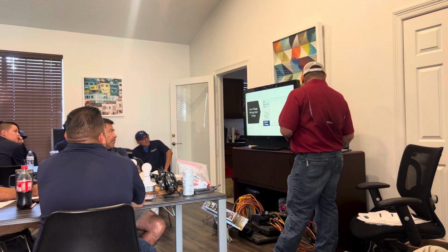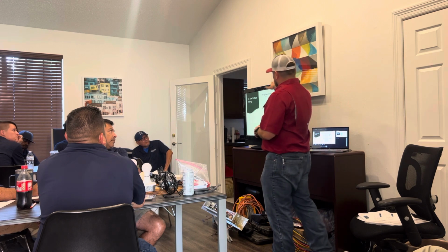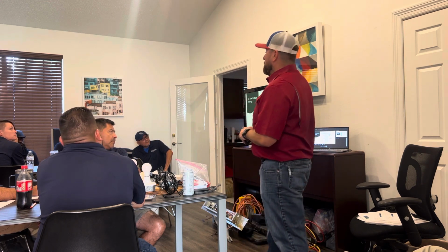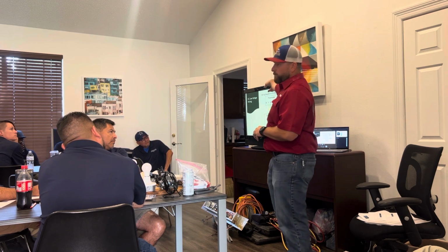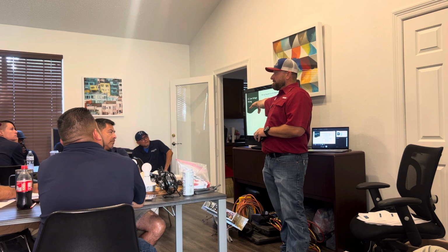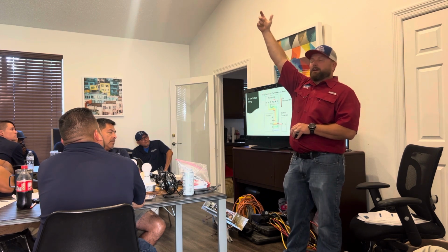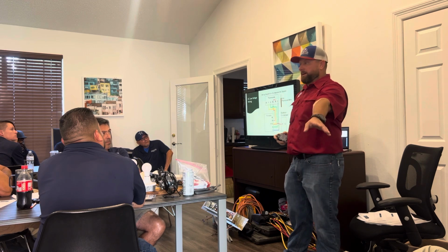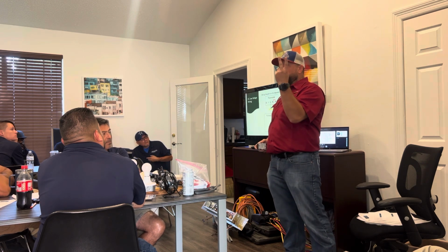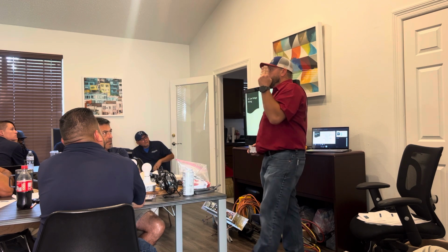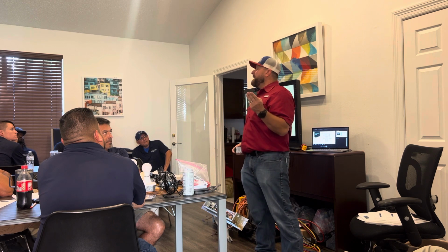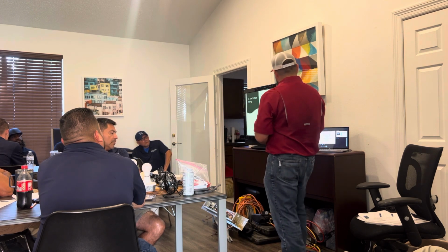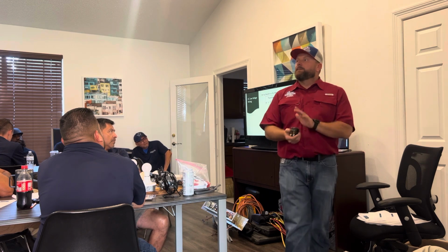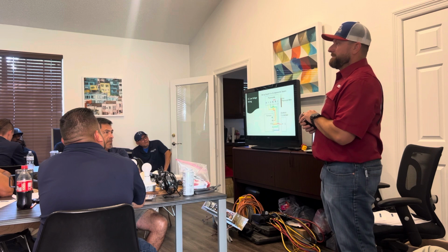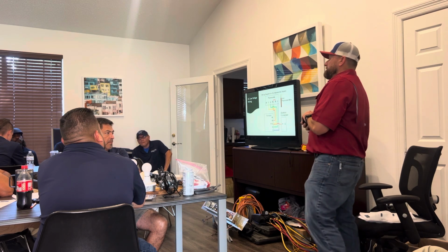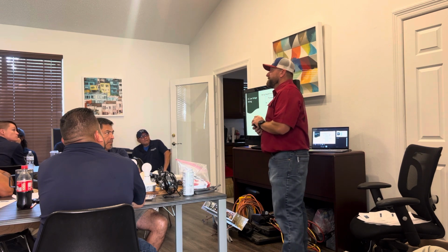Does that make sense when we talk about wiring? You'll have wires coming from the thermostat up to the air handler, and then from the air handler out to the condenser. Most of your properties have 2 to 3 wires coming out. If you ever have to replace the wire, use an 18/8 — it says 18/6 here, but we want 18/8, those are better communicating wires if you have to run them. Those wires are a little bit stronger, yeah.